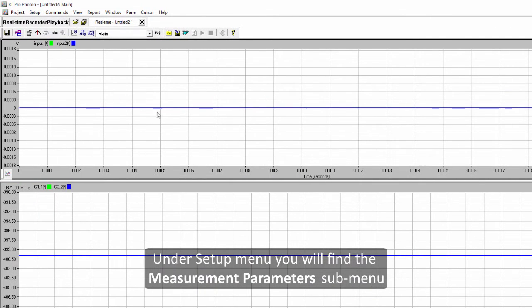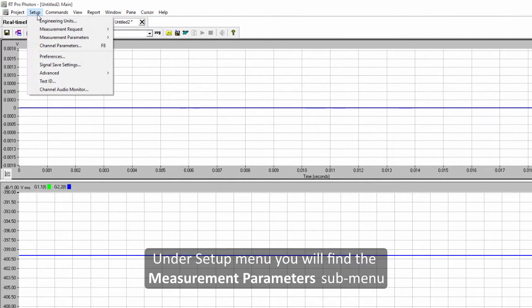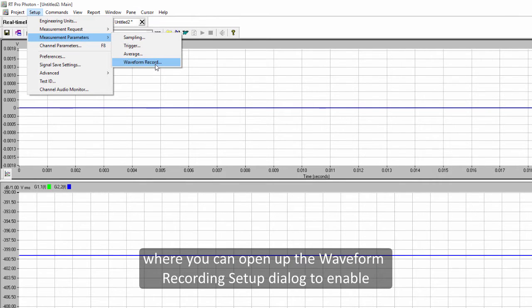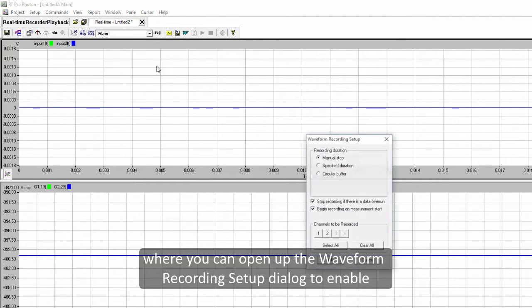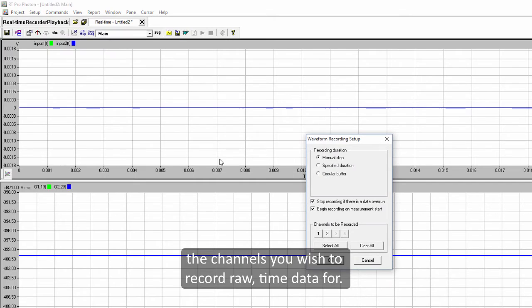Under setup menu you will find measurement parameters sub menu where you can open up waveform recording setup dialog to enable the channels you wish to record raw time data for.